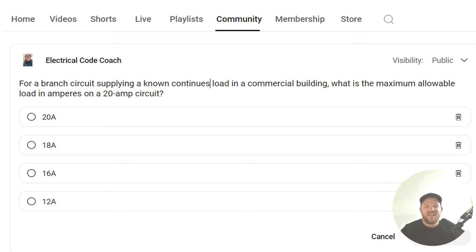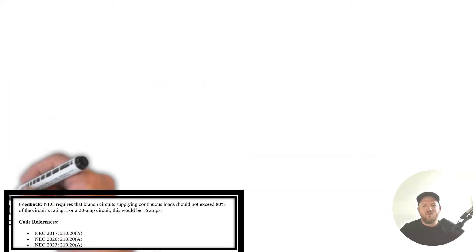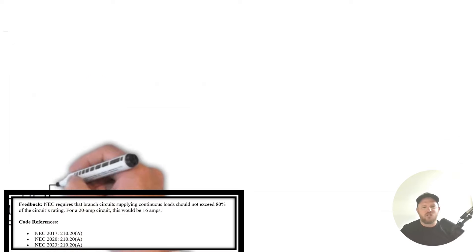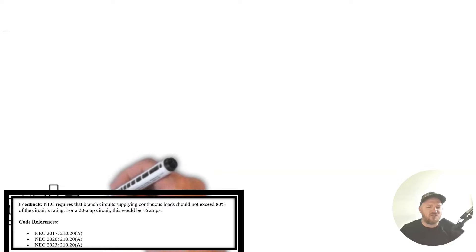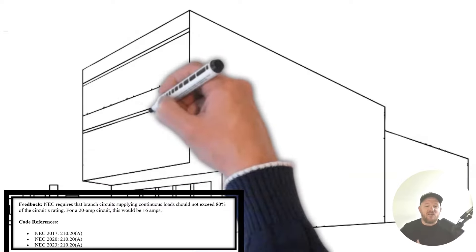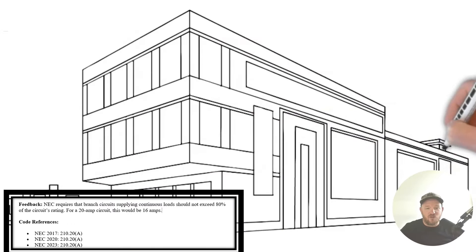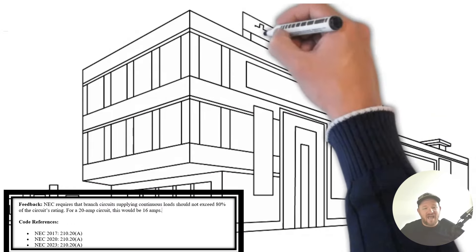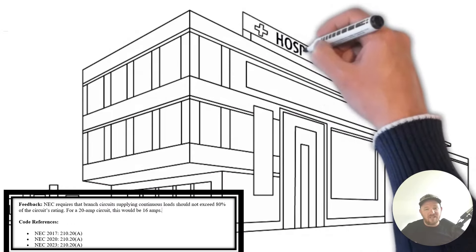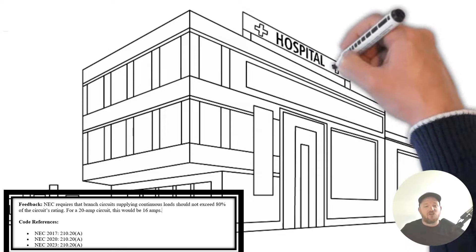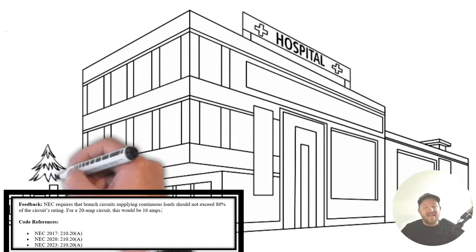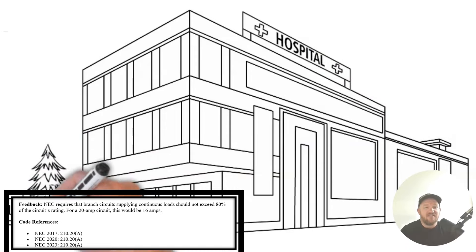The correct answer is 16. Whether it's commercial or residential, if it's a known continuous load, we're going to have to only fill that circuit up to 80% of its capacity.